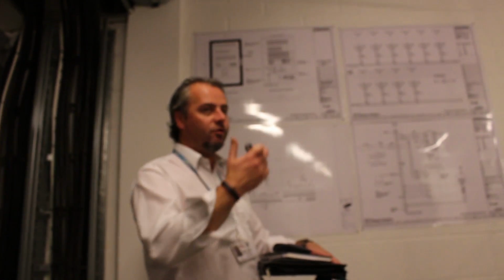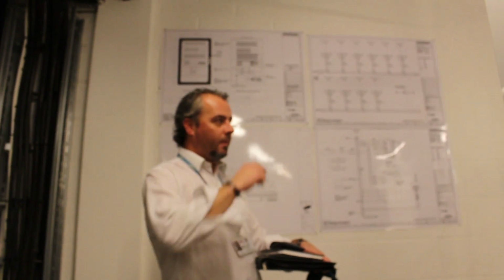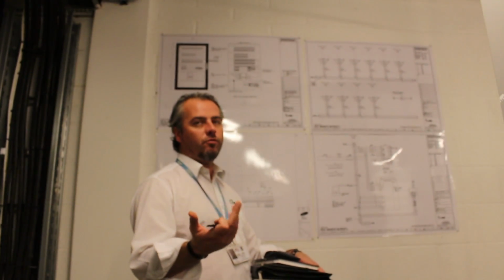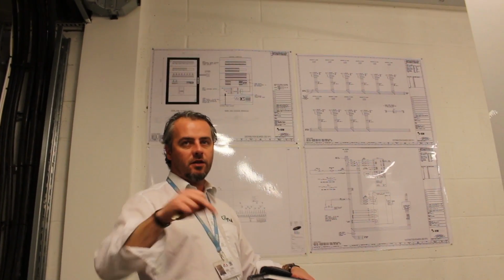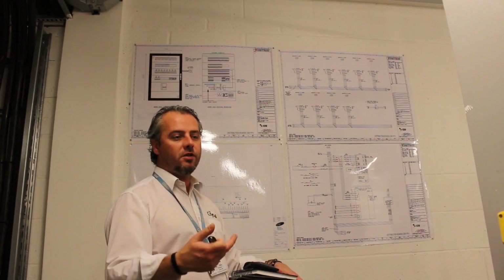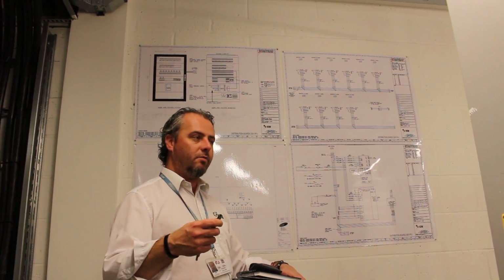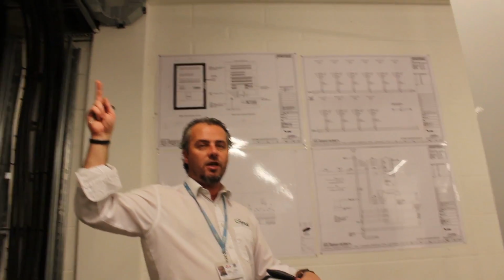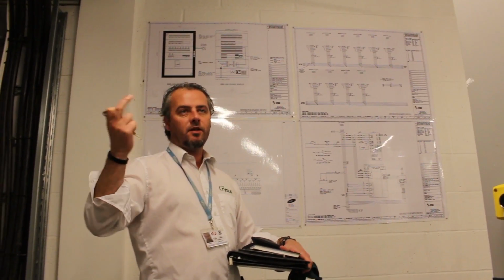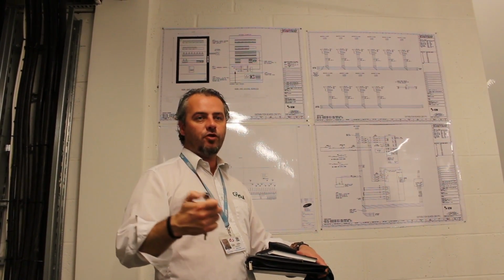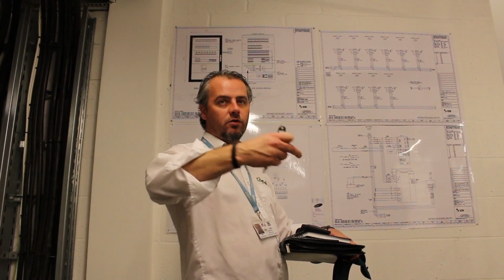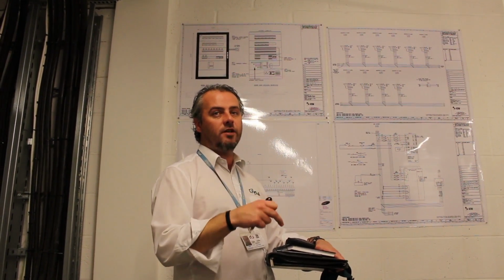They can override it - if you were in one of our meeting rooms and wanted ventilation, we have natural ventilation windows, 150 of them all around that can be open, so you can let them out for natural ventilation. But they could also override the system and open the window if you requested it personally because your room felt too warm. Normally they only open based on an algorithm communicating from the weather station to the building management system, looking at rain, direction, wind speed, and temperatures - only when this algorithm is satisfied will the windows open. Otherwise you have to personally go and open it.